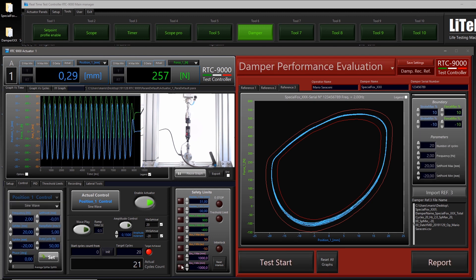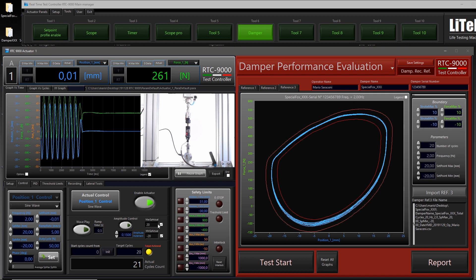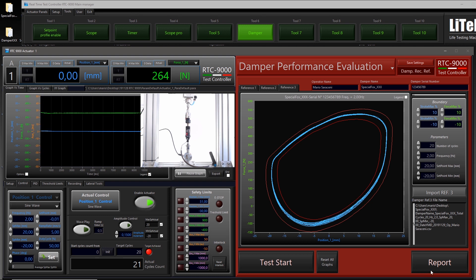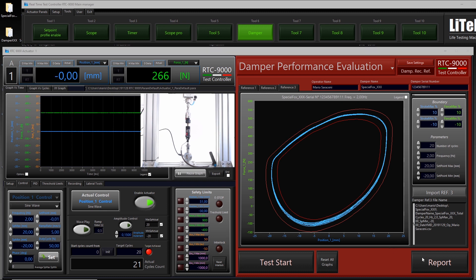The test is now finished. Pay attention — the actuator is always enabled, so for safety stay away from it. Now we will make the report. Put the serial number here; if you put the wrong one, don't worry. When you click Report, everything will be updated. So click Report and then copy the serial number.